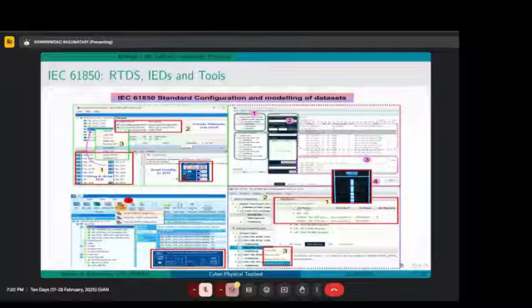After creating the data sets, your relay should get the updated data, so you send the CID file. CID means Configured IED Description file, which is the most important file when working with IEC 61850. You just right click and send the CID file to the relay.